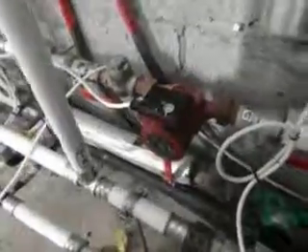Looking at the return line for the heat pump, look at the diagram there first. We have, starting at the heat pump, coming in valve 16. There's valve 16 there, the return on the heat pump, valve 15, and then the pump, which will need to be made bigger. That pump will be swapped actually with this red pump up here, because the red one is bigger. And there's the return coming back into the point at T-piece TB. So we can see the heat pump return there. Yeah, there it is, coming back in and teeing in at TB to those valves and that. So that's pretty much what's there at the moment.